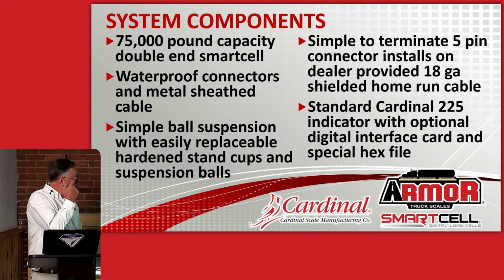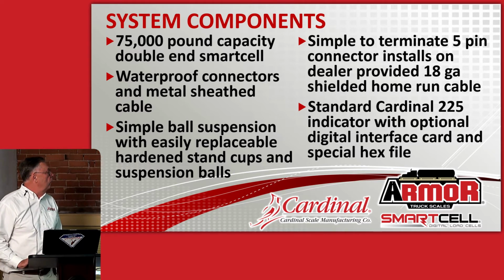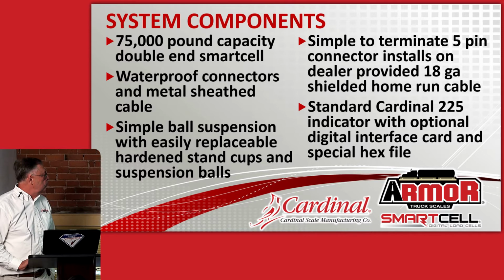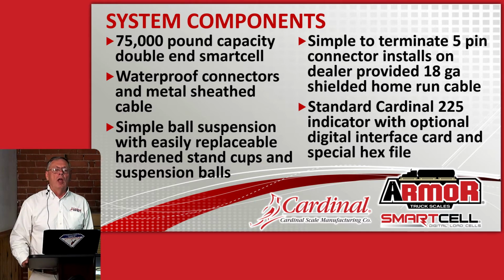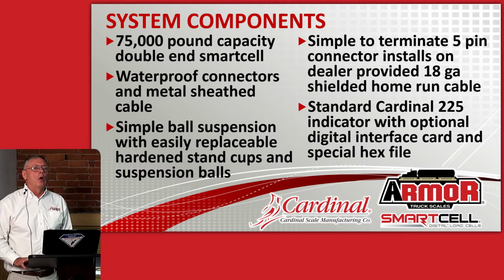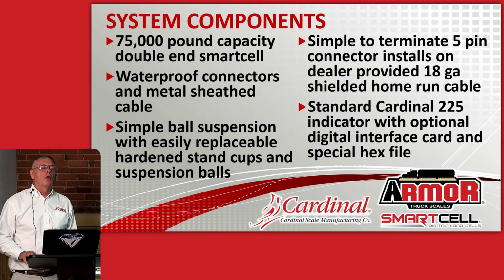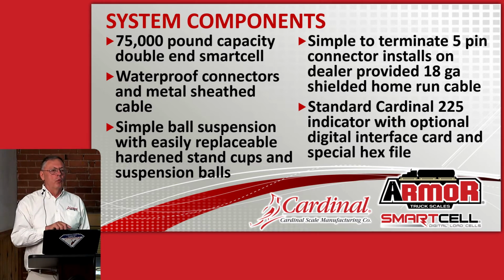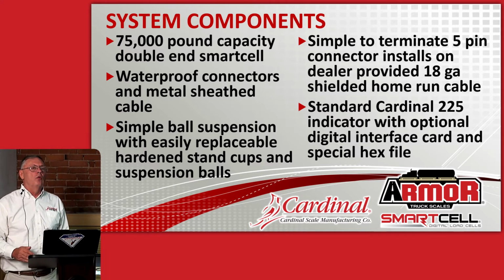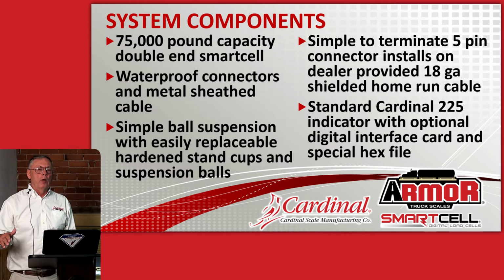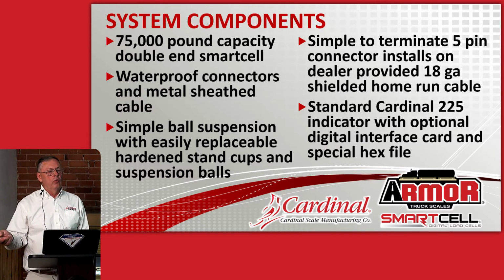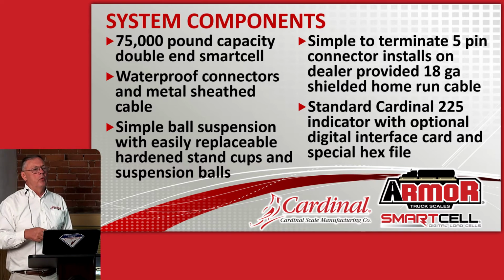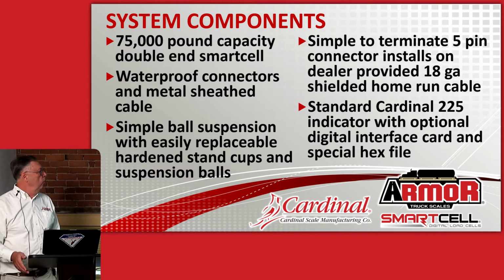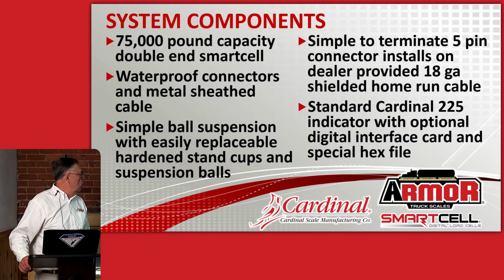The system components: we've got a 75,000 pound capacity double-ended SmartCell, waterproof connectors, and metal sheathed cable. On our original armored truck scale, all of the load cell cables were run in conduit. So if you had to change a load cell, first thing you had to do is take the cover off, get into the junction box, open up the junction box, disconnect the load cell cable, pull the cable through the conduit, change the load cell, pull the new cable back through the conduit, do all your connections, and it just took a long time to change a load cell.